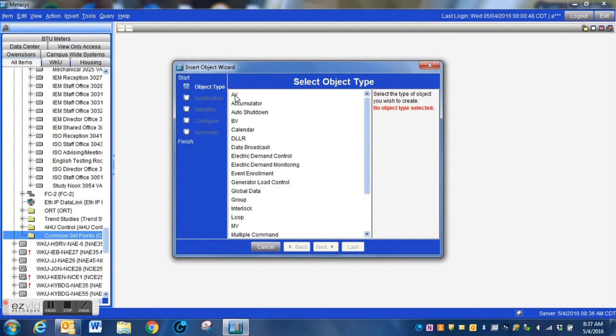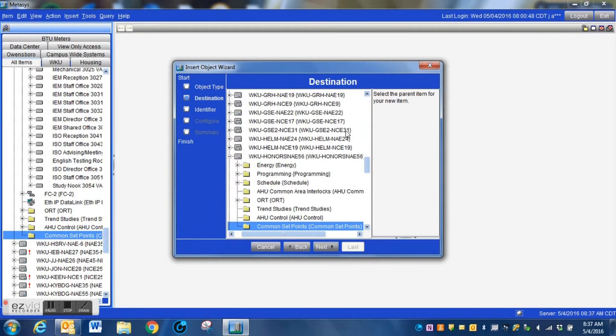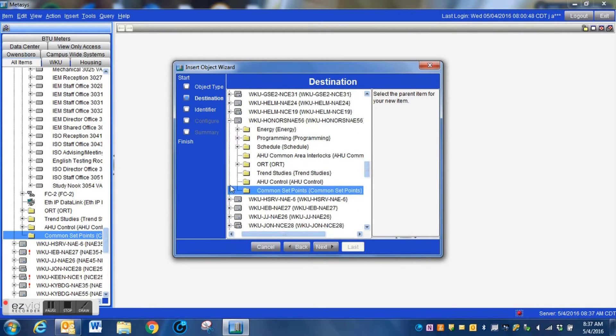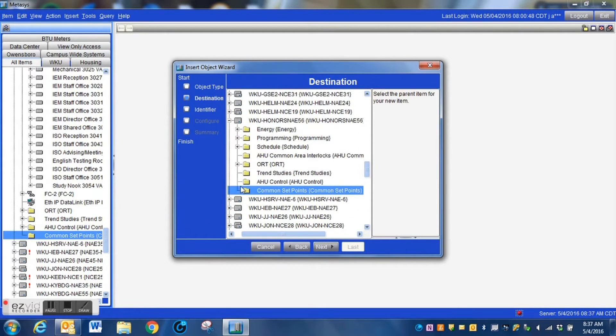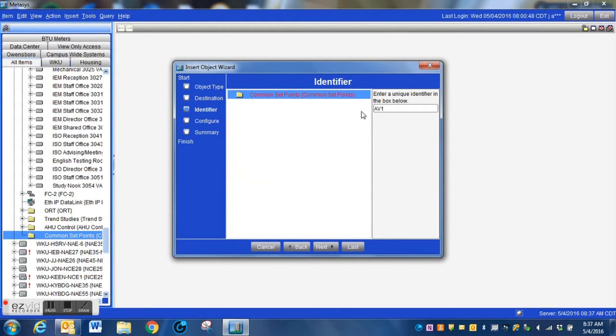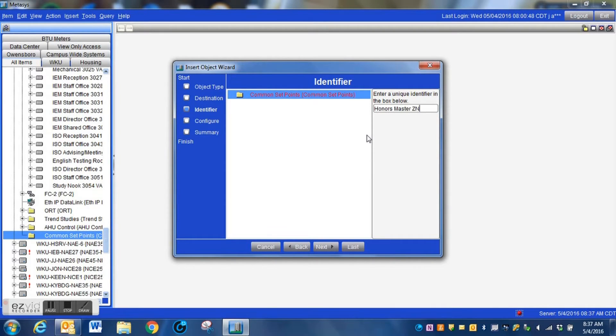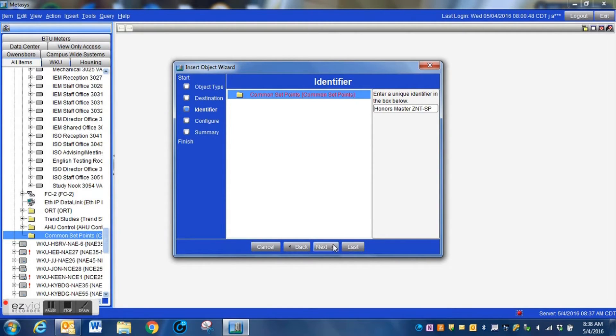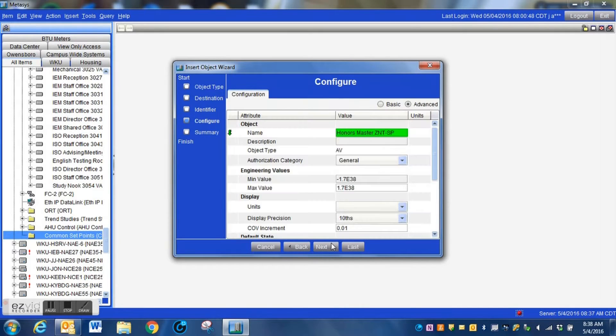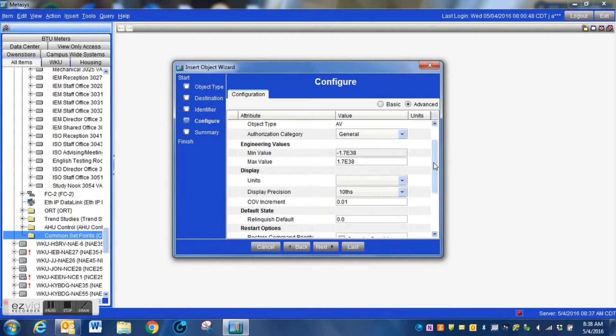The first thing we're going to do is to put an AV point, an analog value. We have to have an analog value for entering the temperature that we want shared among all the controllers. Of course, we're highlighted here as far as our location. We're simply going to select next and we're going to give this a unique name. Since this is something that is going to control the entire building, we want to identify that in its name. We want to let people know if they see this that it will change the entire building in some way. This is a master common zone set point. There's many things you can name it, but name it something relative to your system, something that is familiar to you.